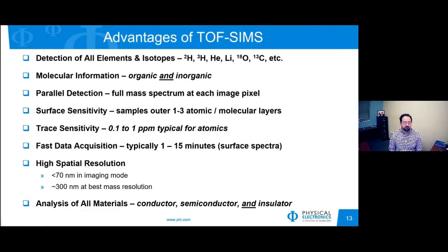How TOF-SIMS fits into the mass spectrometer regime is that it's an imaging mass spectrometer, so you get images as well as spectra for this technique. How it works is that the primary ion beam rasters over the sample, and the electronics store the position where each spectrum was generated as the beam rasters across the sample. So a mass spectrum is generated at each pixel, and then you can map it back to reform the ion image of the mass spectrum.